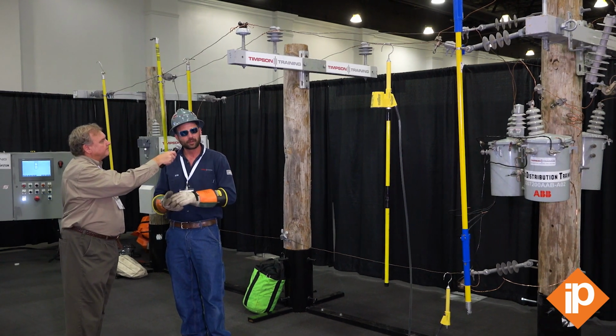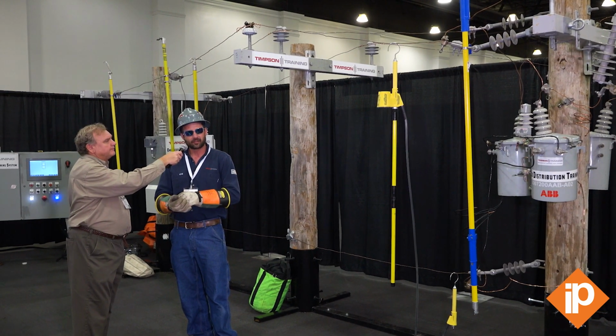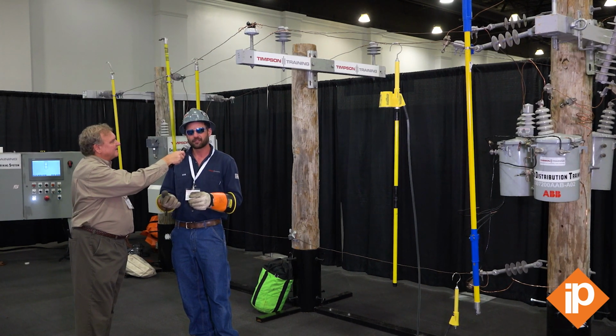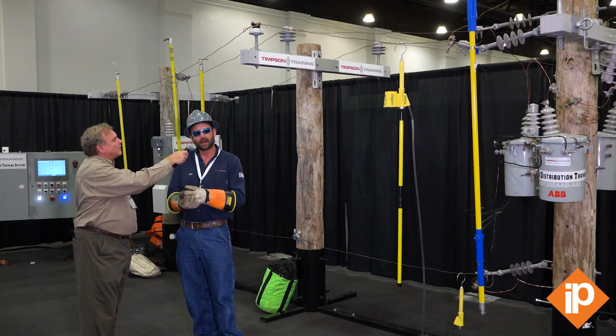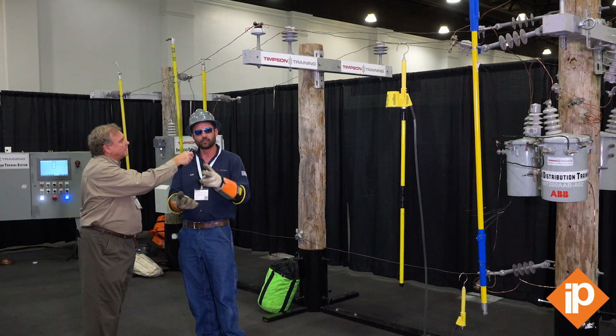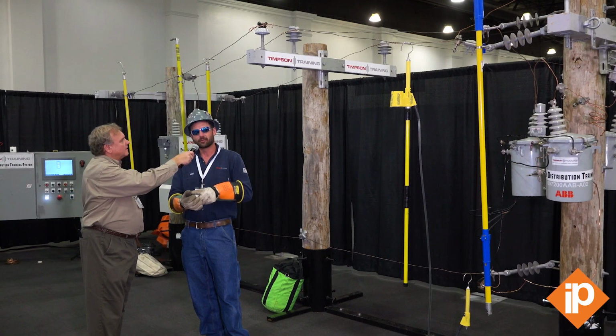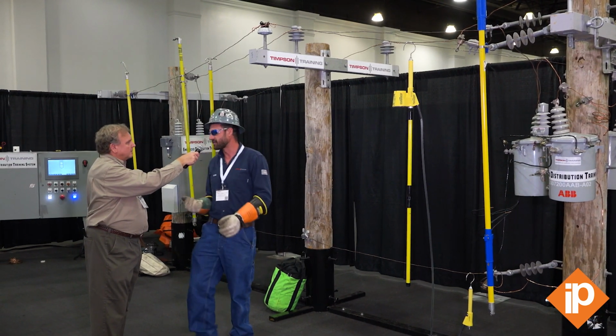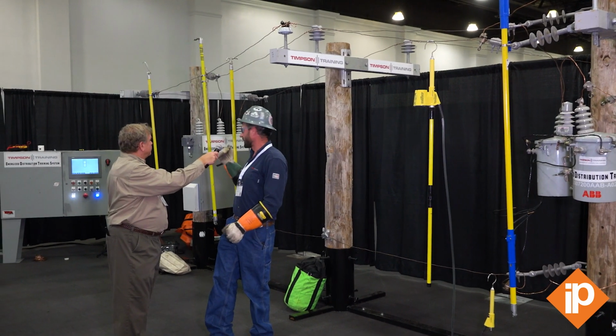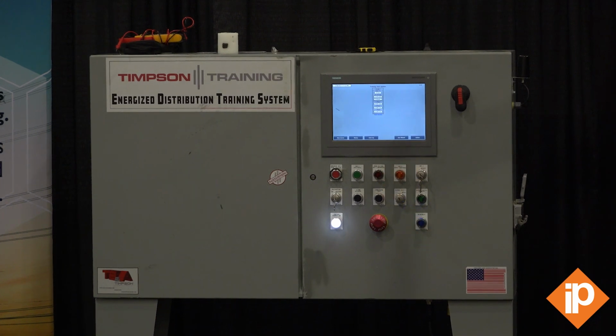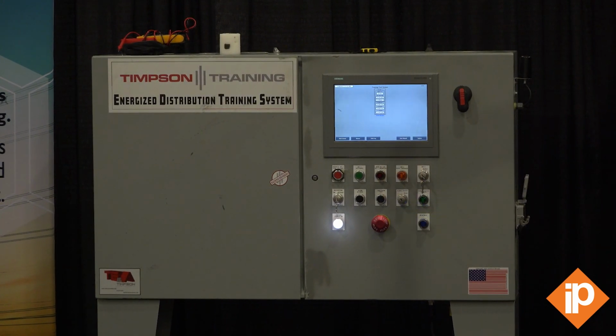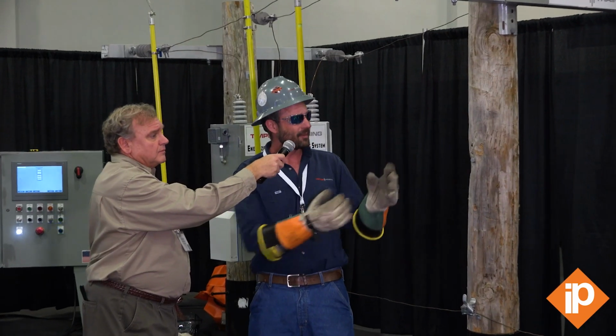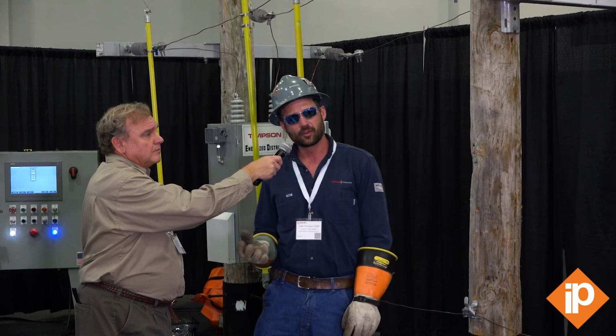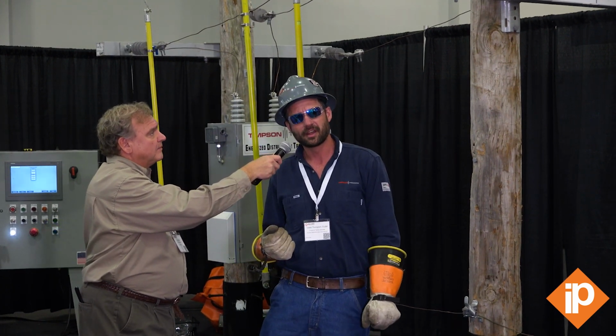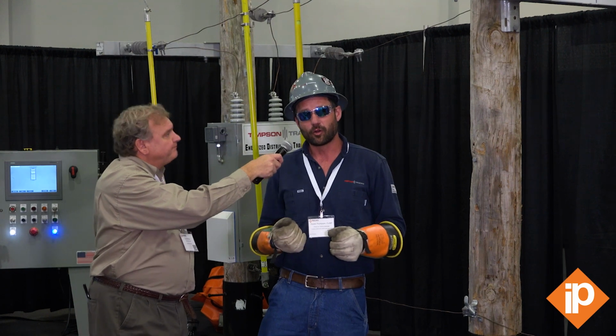It's also SIL 3 rated, so it's rated to protect life, 1 in 10 million chance of failing, and it's redundant by 3, so if one of the relays fails, there's 2 more to back that up. There's a main relay, and each relay has 2 stages. With this system, you can put in a training yard and energize basically any amount of wire you want. This is a 1-circuit panel, which means you have one 3-phase circuit. You can put about 3 transformer banks on it, and it does have remote control.